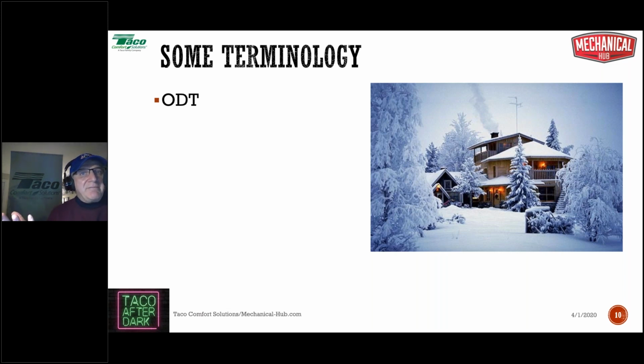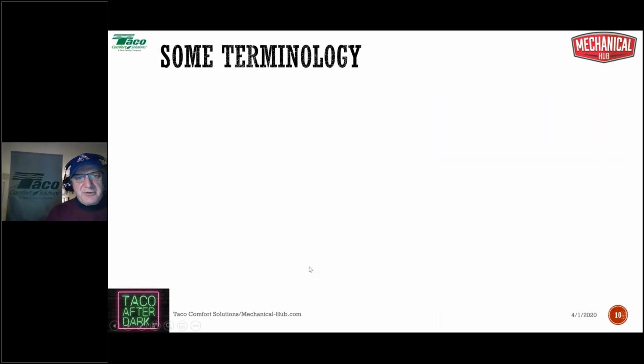57, 75. I've got about 23,000 BTUs sitting around looking for something to do under design conditions. You're fine. It's not a dramatically oversized boiler given what sizes we have available today, so don't get too worried about it, or about exaggerating that outdoor design temperature. That's just something to think about on your end.